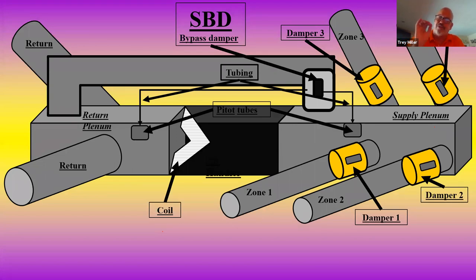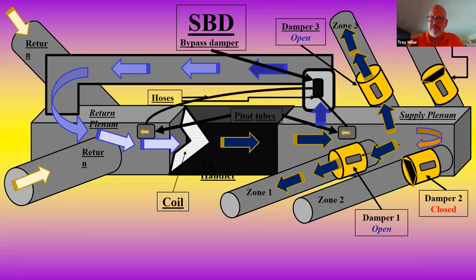This is going to capture true design static with the accuracy of a digital manometer and maintain it 365, 24/7. That's exactly what we want to happen. So when I'm only calling from these two zones, where'd my pointer go? I'm only calling from this zone and this zone. These are shut. I'm going to deliver the exact same static pressure through these runs as I would if all four of them were calling, because I've captured design static and I'm maintaining it no matter what the scenario is in the duct system. This makes sure our system runs at peak efficiency at all times. Okay?